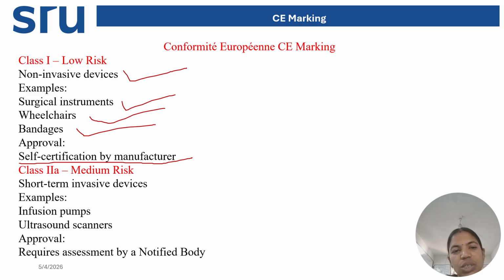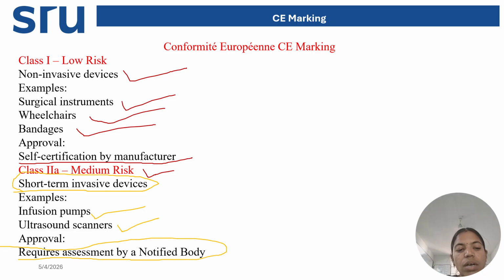Class 2. Class 2 is again two types, class 2A and class 2B. Class 2A is called the medium risk category. Short term invasiveness means for some period of time there is physical contact with the body. For example, infusion pumps, or an inhaler that will be inside the mouth of the patient for some seconds or a minute, which means it is inside the body. That is short-term invasive, and ultrasound scanners. All these are categorized as medium risk, class 2A. These need approval, requiring assessment by a notified body, not only from the manufacturer.